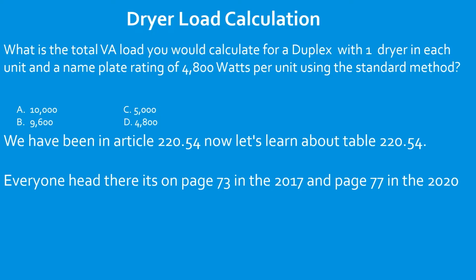If you're in a different code cycle, don't worry. You can find it. Just head to Article 220.54 and then look around for the tables, and you'll find Table 220.54. The information hasn't changed in the last 10 cycles, and it's not going to change anytime soon. So this is going to be universal across the board. So with that being said, we go ahead and head there.